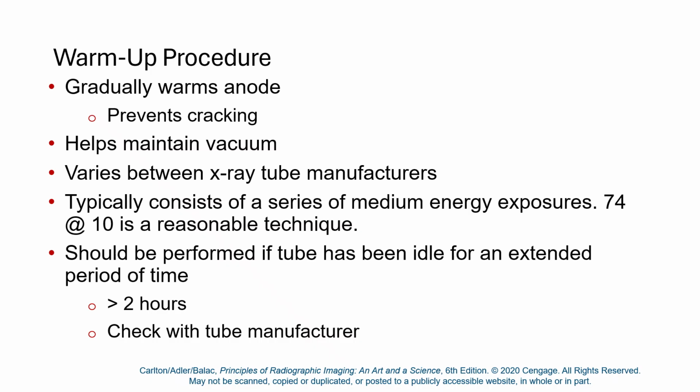It also helps maintain the vacuum of the X-ray tube, because it prevents the tungsten from sublimating. Sublimation is when you skip the liquid phase and go right from solid to gas, and it can happen with most materials if you dump in too much heat too fast.